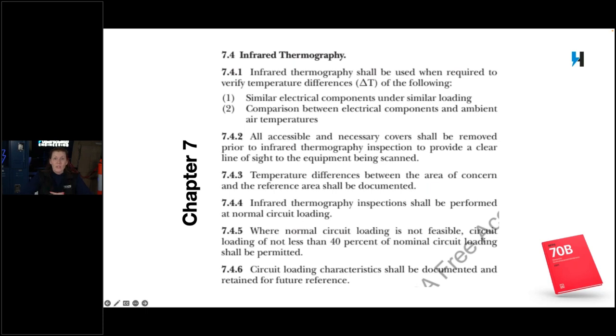Where you can, temperature differences need to be documented, so think about reports or some way to circle back and reference that information later. They need to be performed at normal circuit loading. In other words, don't schedule it for your shutdown week when nothing's running because you're doing all the other maintenance stuff as well. That doesn't give you a solid look at what the loads are actually like and what the normal temperatures you should be seeing will be.